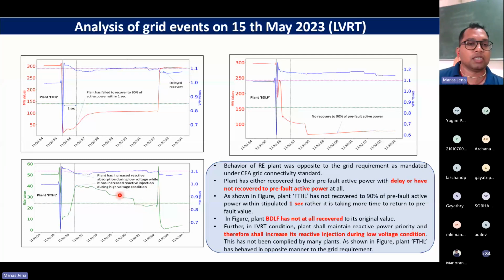Very difficult scenario. You see, already this blue color is more than 1 per unit, right? When it is more than 1, that means you have a high voltage scenario. You are supposed to absorb VAR, not inject VAR, correct? So there also you could see this plant is not strictly following the grid code, whatever is mandated. Let us go through it. We could see all these three graphs.